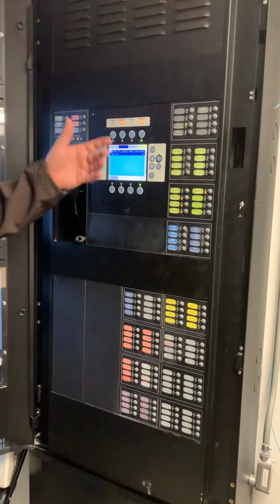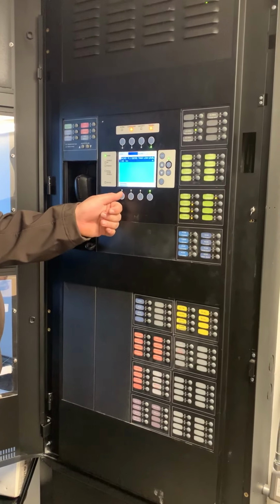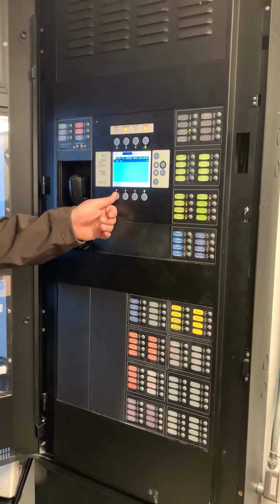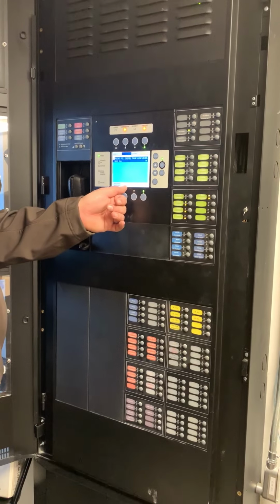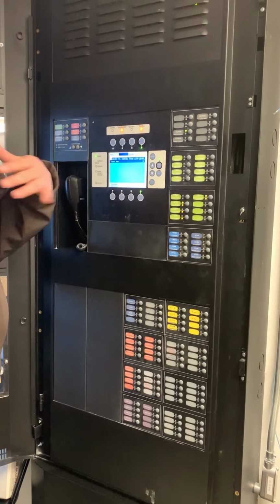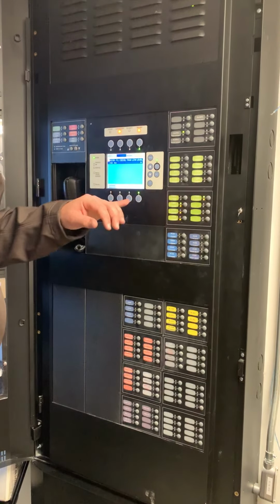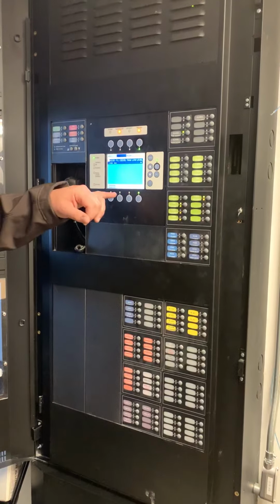But if you have an alarm, the screen's gonna be red. It's gonna say acknowledge alarms down here. This button will be green. You hit that, and then this is gonna have silence audibles. We click that, that's gonna be green. You click that to turn off the speakers. And then you can reset the system.